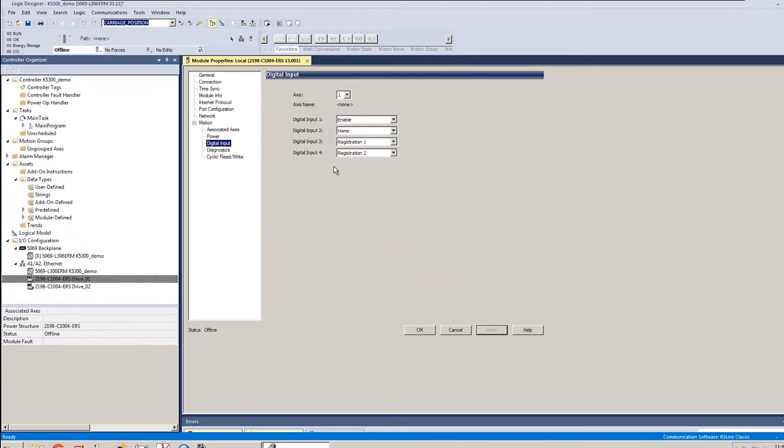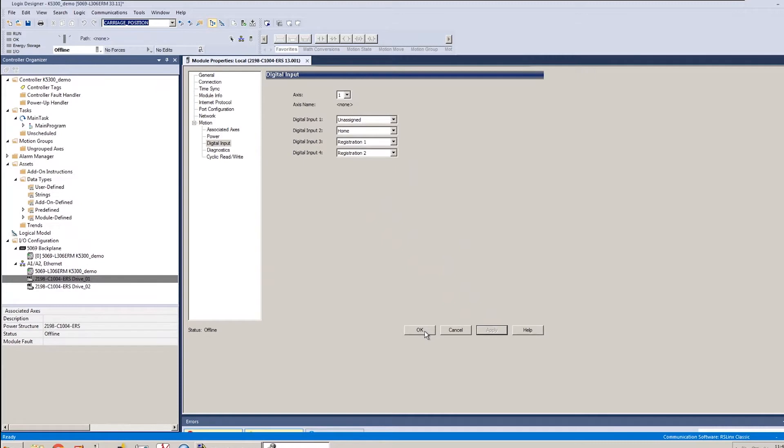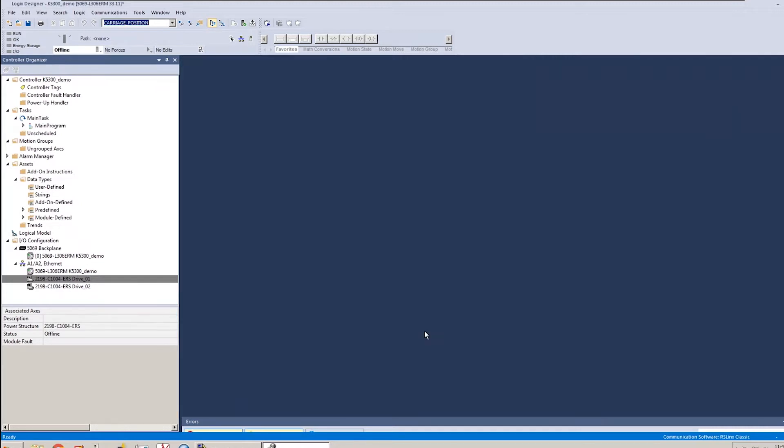And then the second thing I want to do is go to the digital input tab, and by default, input 1 is set to enable. If you don't have anything wired up to input 1 and it's set to enable, the drive won't run like that. You have to go and unassign that or set it appropriately, or if it is used as an enable input, you just have to make sure that it's turned on in order to use your drives.